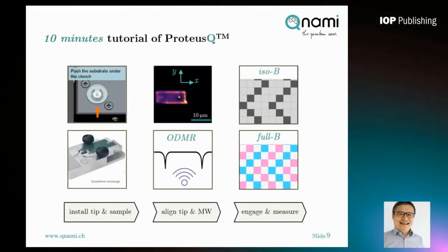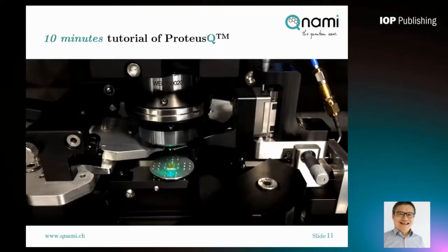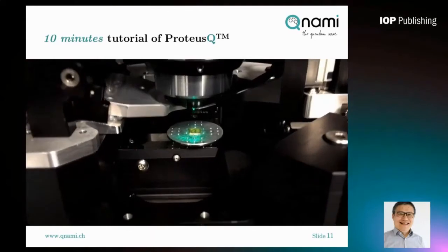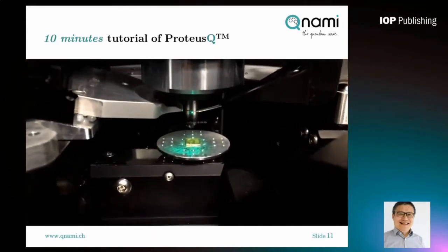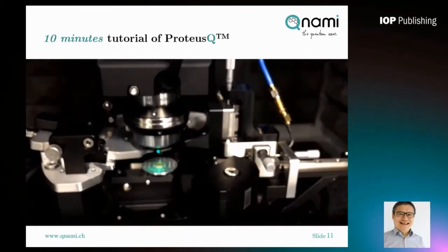Now I'd like to spend a few minutes giving you a tutorial of using ProteusQ — from preparing the probe and sample through to completing a measurement. Sample mounting in ProteusQ is very simple: just use a tweezer, grab the sample holder, and insert it into the sample scanner. You can see the sample holder together with the sample mounted inside ProteusQ. Depending on the sample size, you can use a small or larger sample holder. The largest sample you can image using ProteusQ is up to 1.5 inches in diameter.